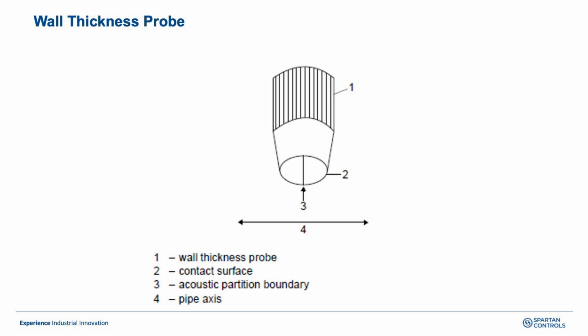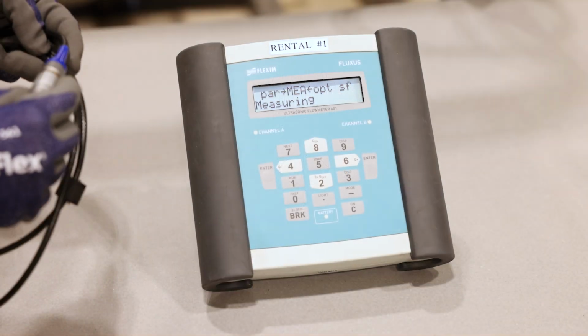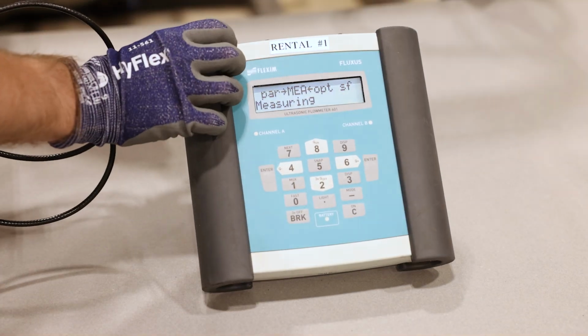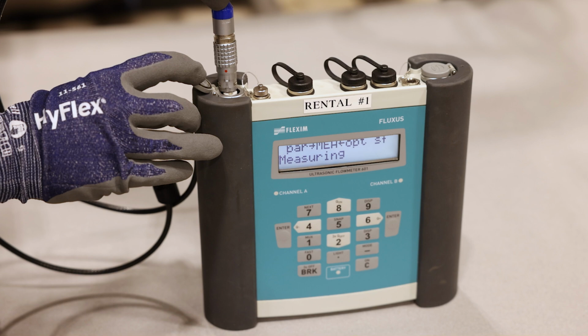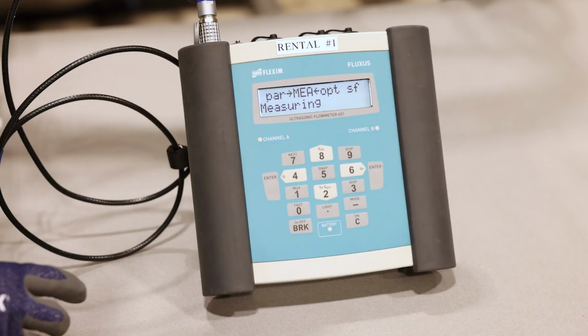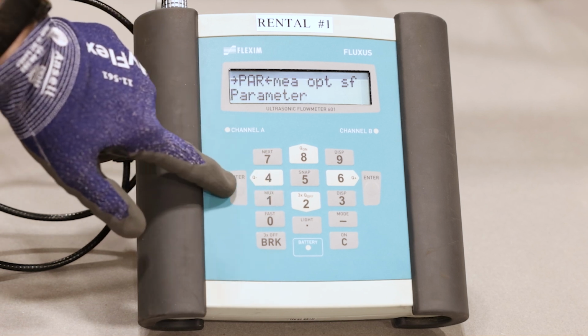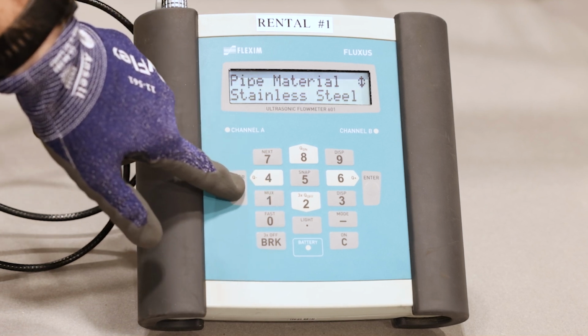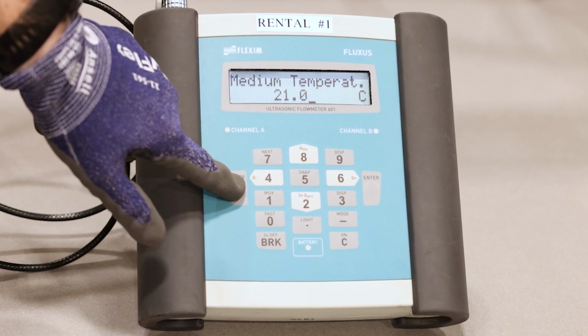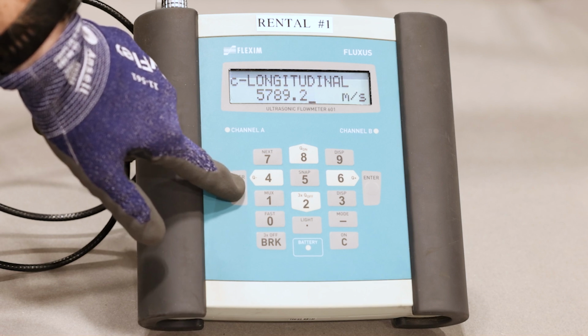In our kit, we have an optional wall thickness probe. We recommend verifying the wall thickness as this could vary from the original specification to its current installation due to corrosion or even buildup. When you plug in the connector, be aware of the red alignment marking on the LEMO connector. Once plugged in, wall thickness detected on A will display and you will hear a beep. The parameters menu will need to be confirmed prior to entering the measuring menu. Leave the default speed of sound entered.